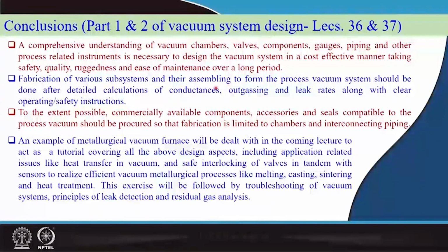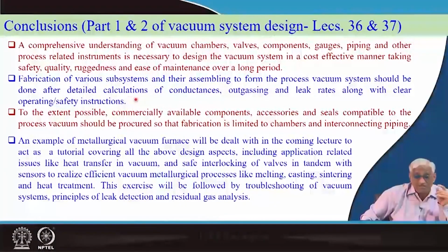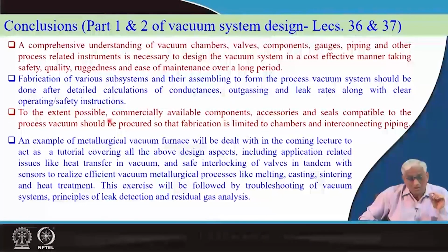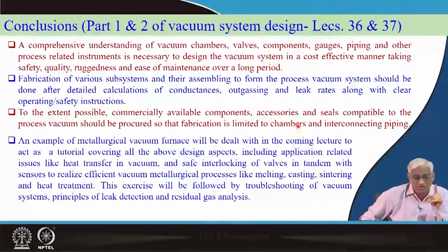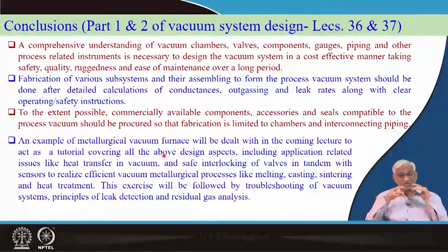Fabrication issues with the reduction of outgassing and leak rates, but maximization of conductances, it is the headache of the system designer. To the extent possible, you have to use the existing components available off the shelf in the market, but high quality components, so that you are limited to fabricating chambers and interconnecting pipes. Then at the end, you have to keep track of the beauty of the system, not only the duty of the system, okay? Because if it looks very odd, the first criticism will come to the designer, then only the operator and all will come into the picture. So, you have to keep track.